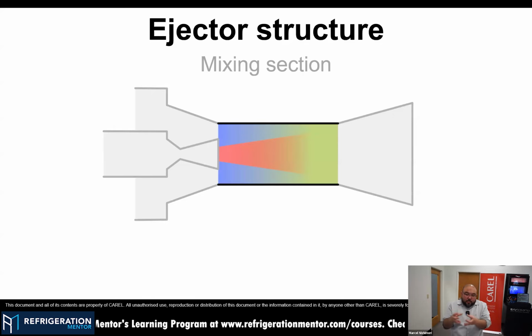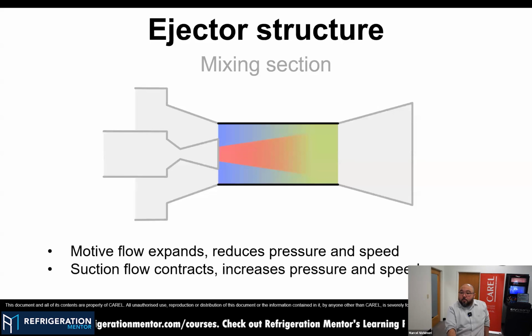We are mixing this inside the ejector, and we are creating, as a consequence, the liquid receiver pressure and mixing of CO2 refrigerant, okay? So in this case, gas cooler pressure will reduce the pressure and increase the speed. Suction pressure will increase the pressure because we are compressing it from 400 psi to a higher liquid receiver pressure. Normally, I would say 460 to 500 psi pressure range. So we are making a compression, and we are also increasing the speed of this refrigerant, okay?